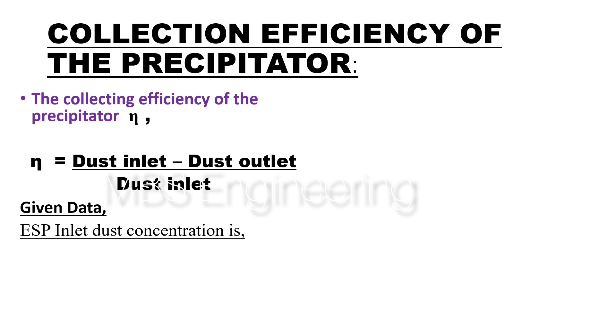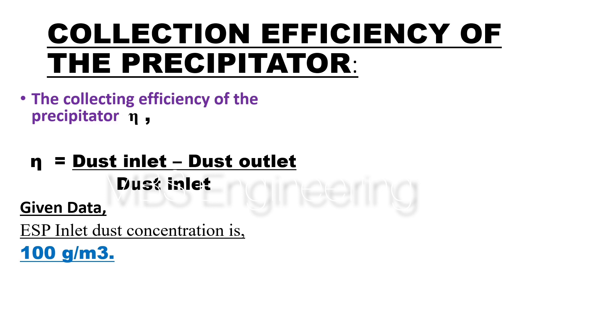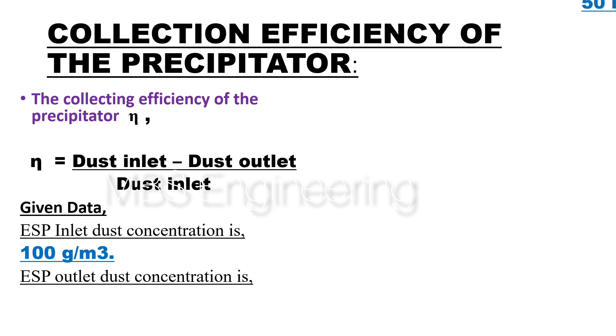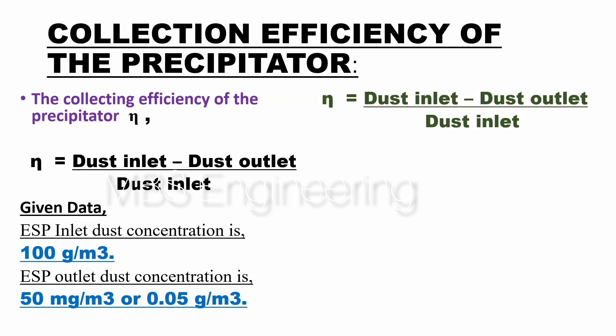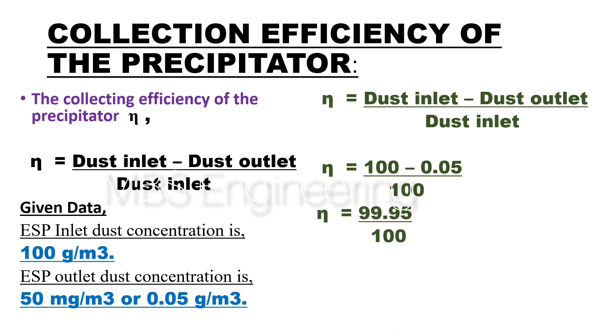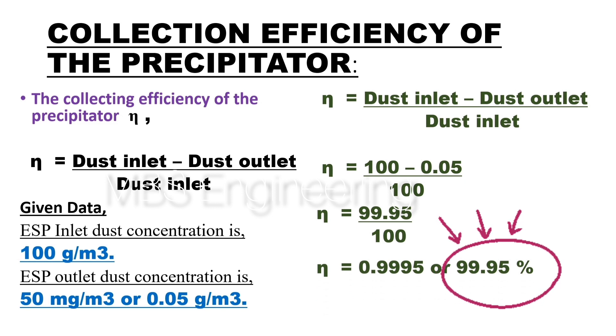The given parameters for calculating the collection efficiency are: ESP inlet dust concentration is 100 grams per cubic meter, and ESP outlet dust concentration is 50 milligrams per cubic meter, or 0.05 grams per cubic meter. The collection efficiency η equals inlet dust concentration minus outlet dust concentration, divided by inlet dust concentration. Please refer to the step-by-step detailed calculation for a better understanding. Based on the given data, the collection efficiency of the electrostatic precipitator is 99.95%.